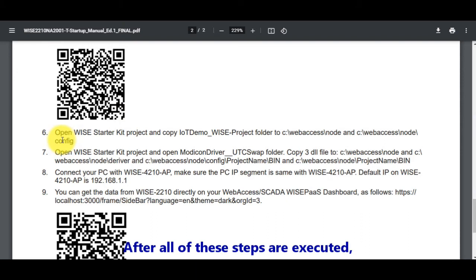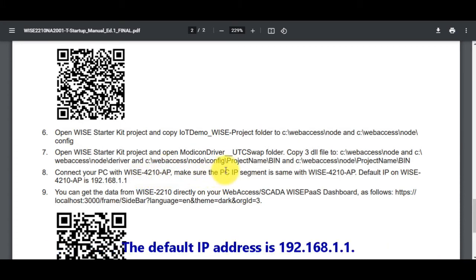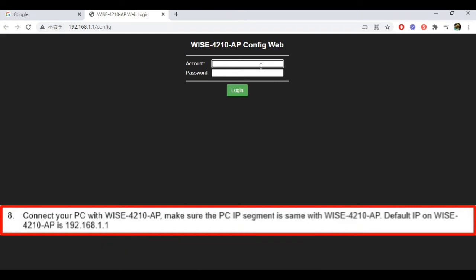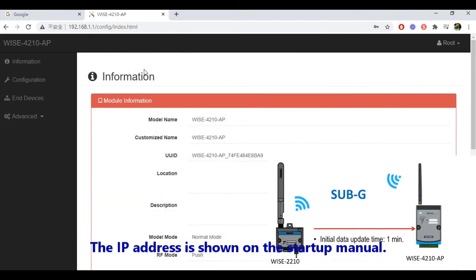After all these steps are executed, connect your computer with the WISE 4210AP. Make sure the PC is in the same IP domain with the WISE 4210AP. The default IP address is 192.168.1.1, as shown on the startup manual.